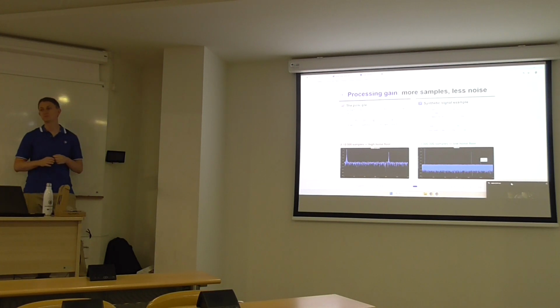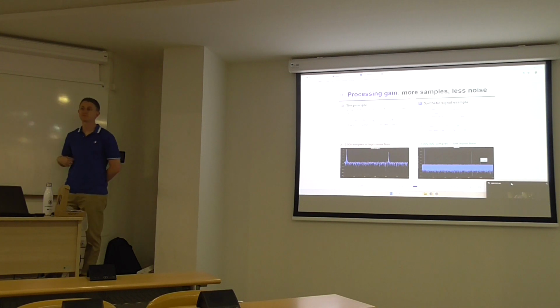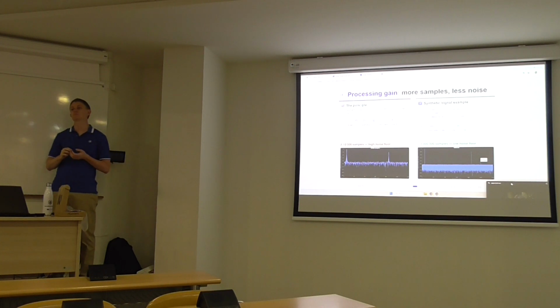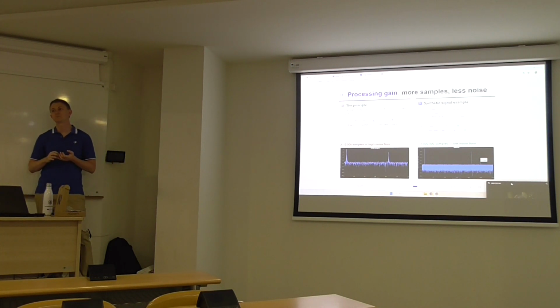The second thing is mixed eccentricity. From your results, you are proving that mixed eccentricity has a lot of mathematical disadvantages as a harmonic to be used for speed estimation. However, in large machines, the bigger the size, the more difficult it is to predict the number of the bars accurately, because you have more design options.